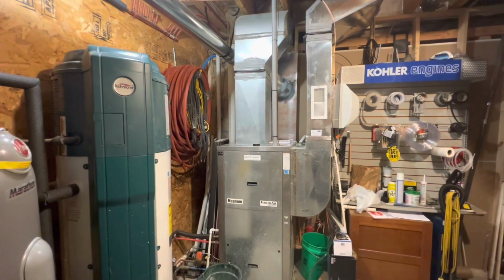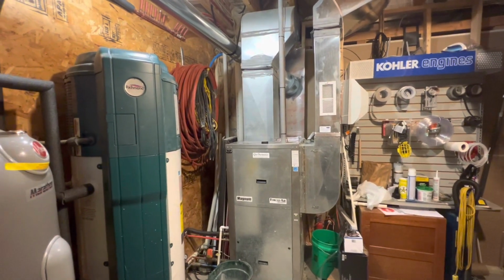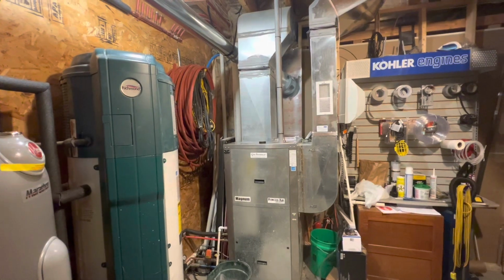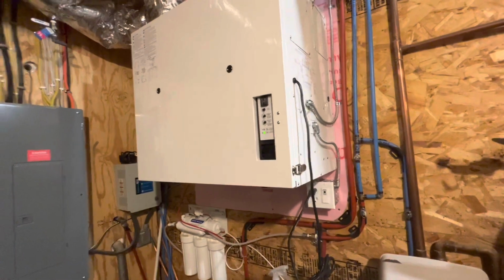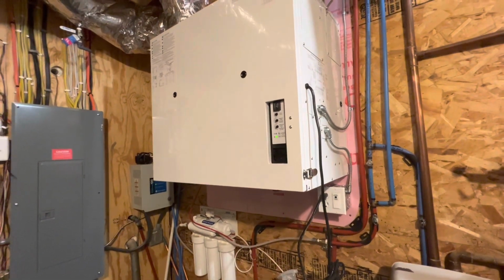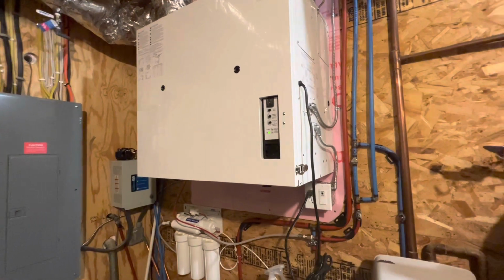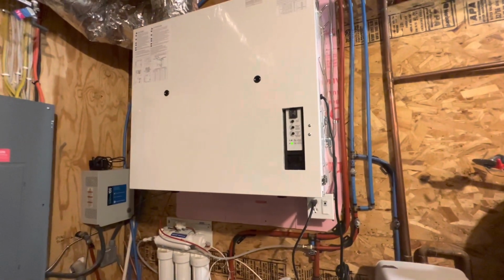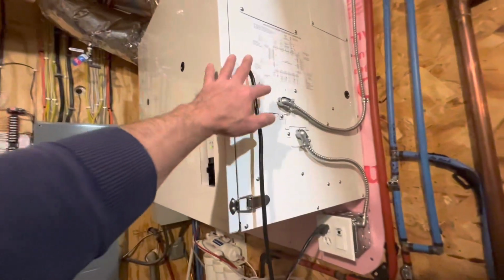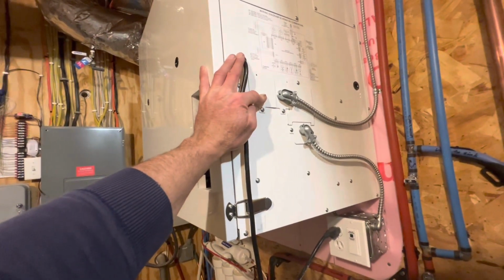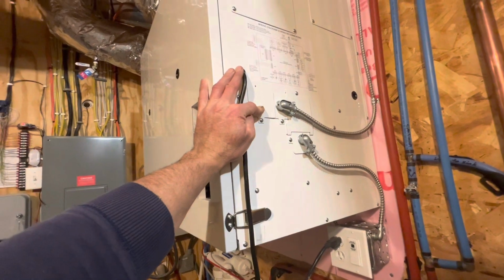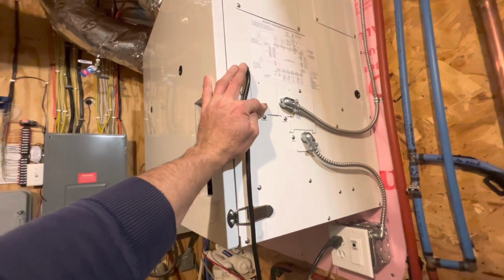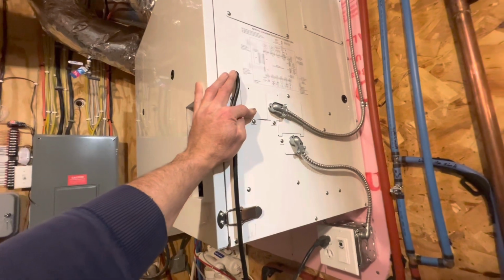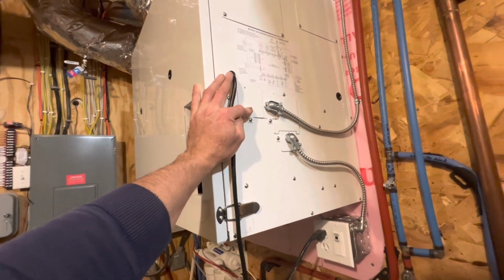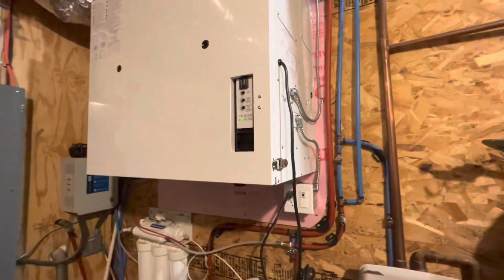Our HVAC unit, I always have the fan going, so I didn't need to wire in the HVAC fan switch for this ERV. Inside this cover, it's got an option where you can wire in your HVAC fan controller, so when the ERV kicks on, it will also kick your HVAC supply fan on.